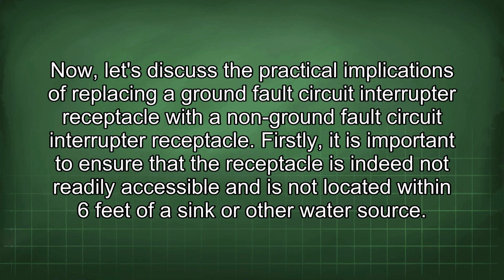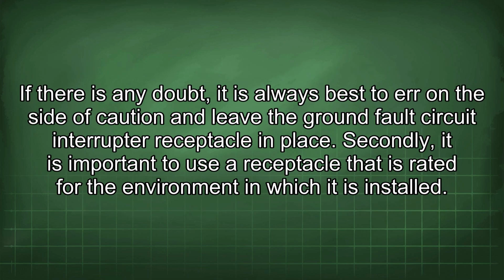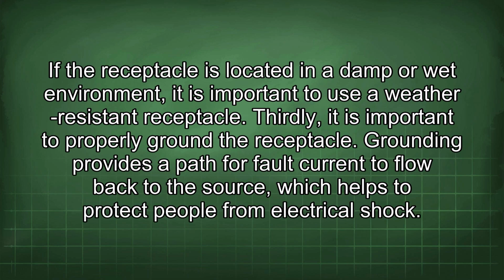Now let's discuss the practical implications of replacing a ground fault circuit interrupter receptacle with a non-ground fault circuit interrupter receptacle. Firstly, it is important to ensure that the receptacle is indeed not readily accessible and is not located within 6 feet of a sink or other water source. If there is any doubt, it is always best to err on the side of caution and leave the ground fault circuit interrupter receptacle in place. Secondly, it is important to use a receptacle that is rated for the environment in which it is installed. If the receptacle is located in a damp or wet environment, use a weather-resistant receptacle.